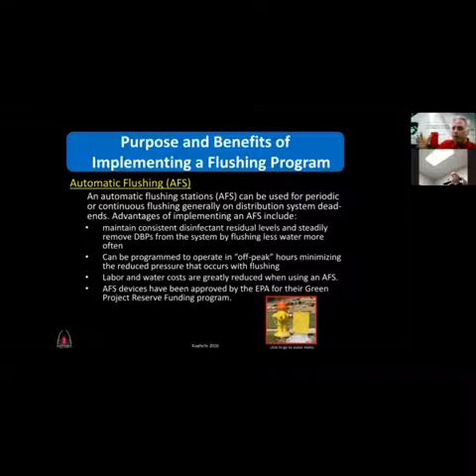For example, Monday, Wednesday, Friday at 2:30 in the morning I flush for 30 minutes — the valve opens and closes. Short shots of water turn the line without a big dump. Another advantage is you can program these in off-peak hours at 2 a.m., without sending someone out to open a hydrant during the day. Labor and water costs are greatly reduced. These have been approved by the EPA as a water conservation device under the Green Project Reserve Funding Program started under the Obama administration.